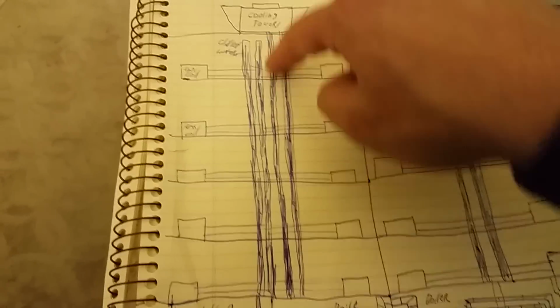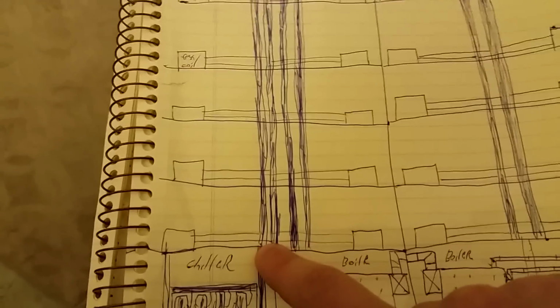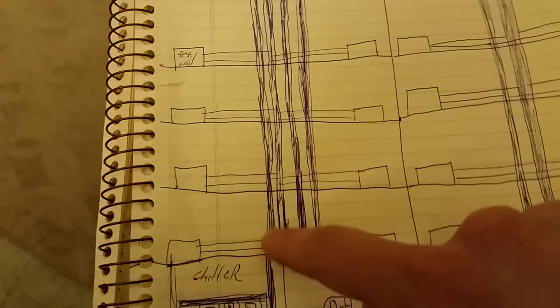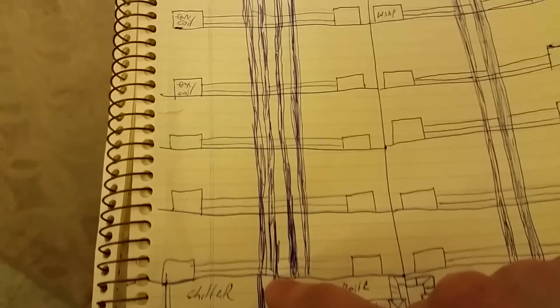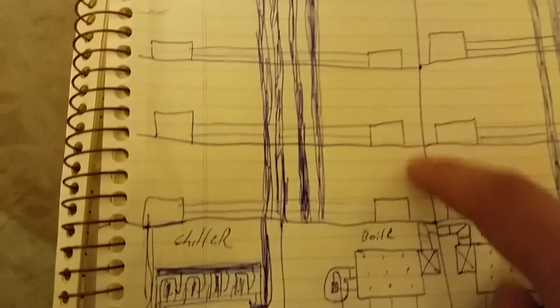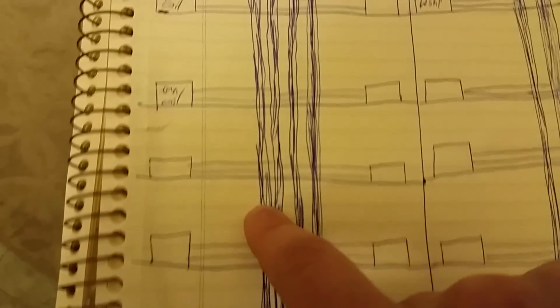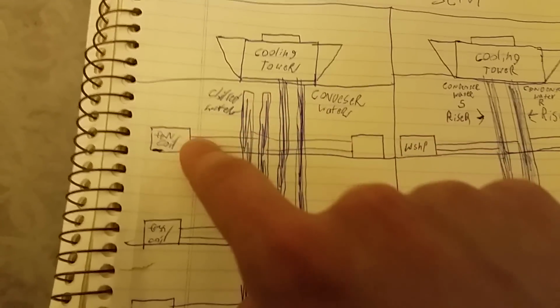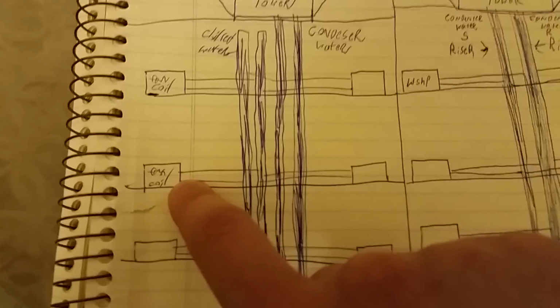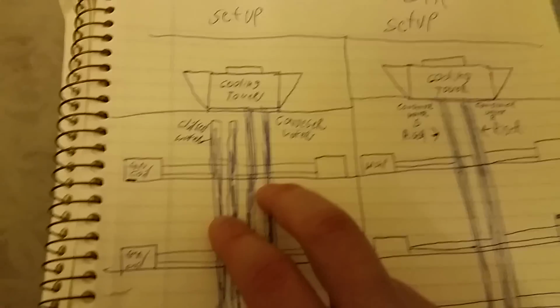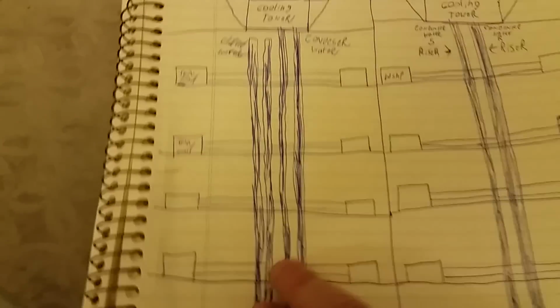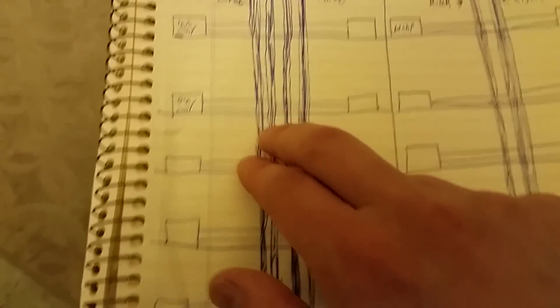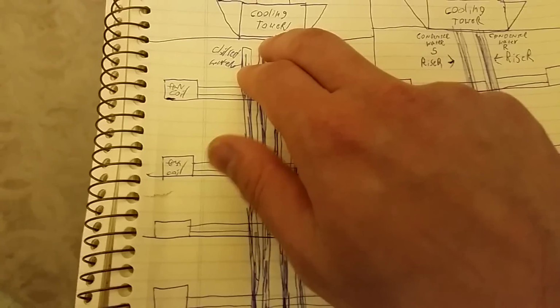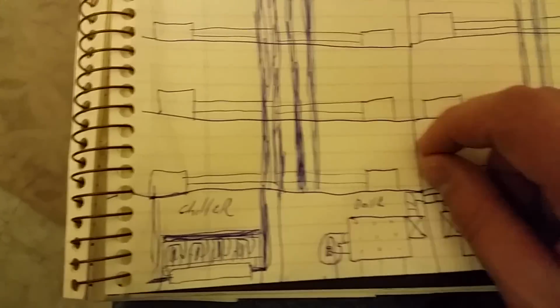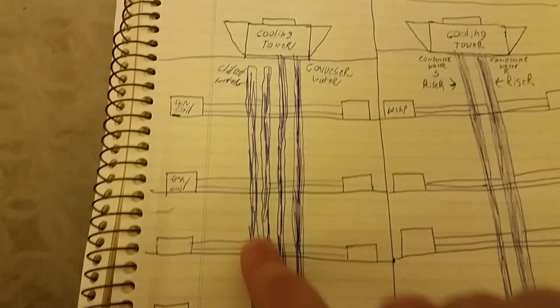You know the refrigerant cycle. Your chilled water side now comes up. You have a supply and a return chilled water line. Again, console units or ceiling units. The chilled water goes up, feeds each fan coil, because it's just a coil and a fan. And this could either be a 2-pipe system or a 4-pipe system. A 2-pipe system is these 2 pipes are chilled water in the summer, and in the winter you switch them over to the boiler and they become hot water.